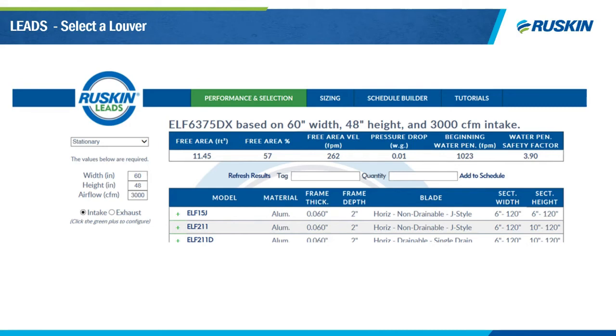One of the first options in LEADS is how to select a louver. Let's say you have a spec, you know what size you need and the amount of airflow, but you're not sure which model to use. You can go to Ruskin's LEADS program and select the Performance Selection section. Choose the category of louver from the drop-down menu — in this case stationary louvers. I know I need a 60 by 48 assembly that needs to pass 3,000 CFM of intake air. By simply clicking on the plus signs next to a model, you can find out exactly how that louver is going to perform. Our ELF6375DX in this situation offers 11.45 square feet of free area — 57% free area — with a free area velocity of 262 feet per minute and 0.01 inches water gauge of pressure drop.